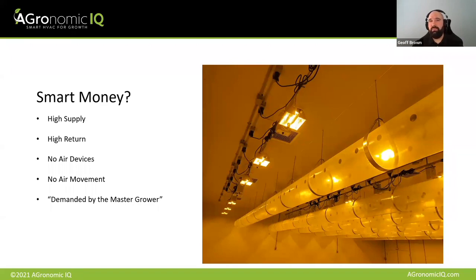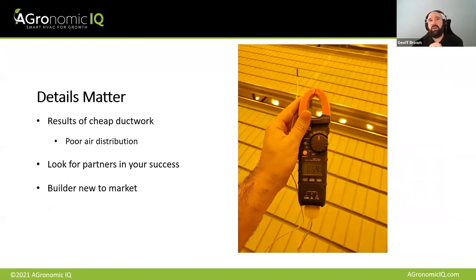But we're talking about maybe 10% of the capital cost of equipment on a particular room in ductwork. And if you're able to save energy in air rotation fans and achieve better results from that room, that little bit of money in a one-time ductwork cost is really smart. In this case as well, of course, different facility, but this is a facility that's got a high return system. Their return up high is reading basically the temperature right off the lights. They are not measuring temperature at the canopy level.